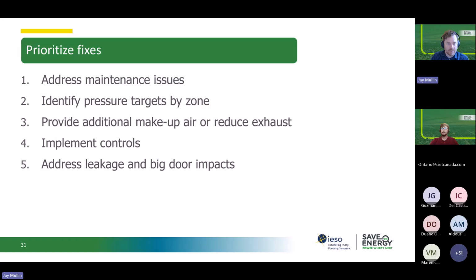Next, you're identifying your pressure targets by zone. If you want slightly positive overall, that is sort of the general recommendation. You'll usually want loading docks neutral or slightly negative pressure to the rest of the facility, so that odors or truck fumes aren't coming into the rest of the plant, and that dirty process areas are negative pressure relative to cleaner areas, so that it's not pushing the dust or the fumes or exhaust into those other areas. So having those targeted on there. And then the next thing is looking at providing additional makeup air to match exhaust, or vice versa if it's balanced the other way around.